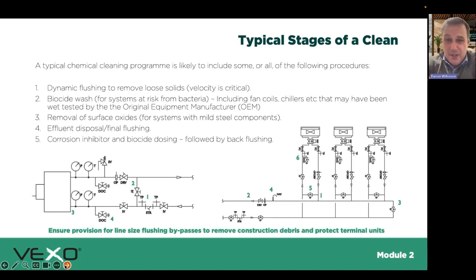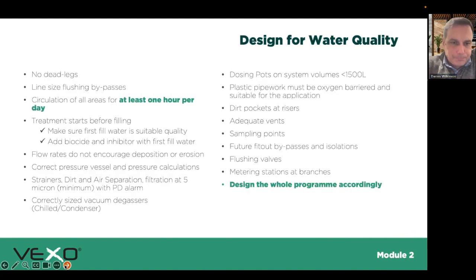Then when you think about cleaning any surface oxides, different types of cleaners are available, particularly if you've got steel. They run the cleaning agent around the system for a period of time. And then finally they need to flush that. Need to consider effluent disposal as well, within the specification. Can you dispose, or do you need to bring off-site bowsers? But once that cleaning agent and the biocide is flushed from the system, they would add the inhibitor and a biocide typically, and then bring online each of those fan coils by back flushing at the same time. Any water loss is made up with inhibitor and biocide.